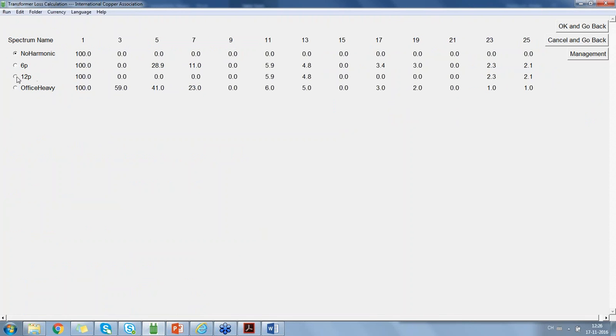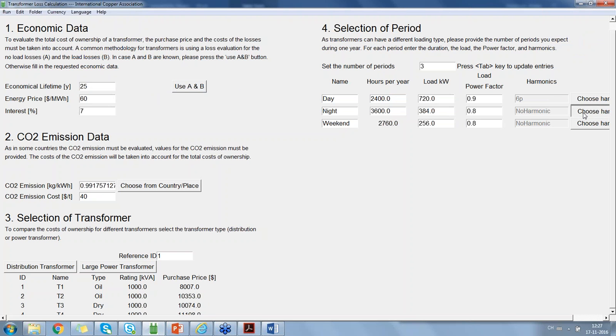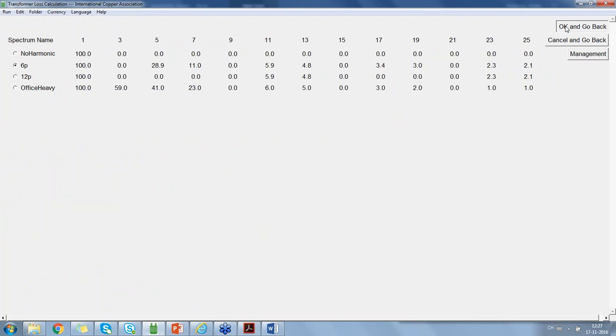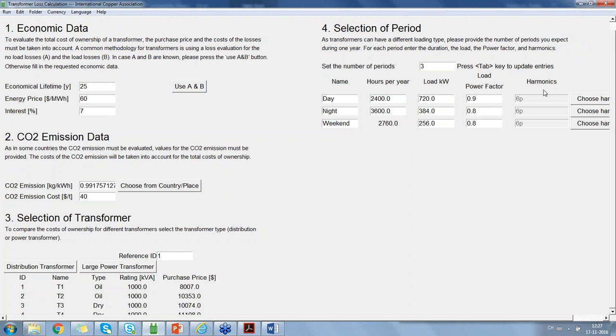I go back to this one and say, okay, let's assume that we have a 6-pulse transformer, meaning we have a lot of 5th and 7th harmonics within the current. I will do it for each period, of course. Select the 6-pulse, and also for the last one select the 6-pulse. So now I've made the same transformer as before. The transformer before didn't have any harmonic loading, and now I've added a harmonic loading of a 6-pulse transformer. If we run it again, it will show me immediately the results.